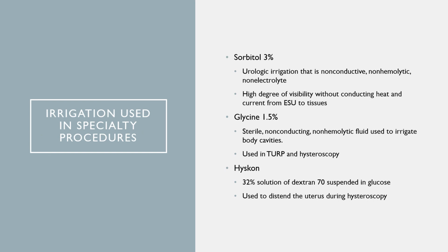Okay, moving on to sorbitol, 3%. This is a urologic irrigation. It's non-conductive, it's non-hemolytic, and it is also non-electrolytic. It has a high degree of visibility without conducting heat and current from the ESU to tissues. So we use that a lot in urology.